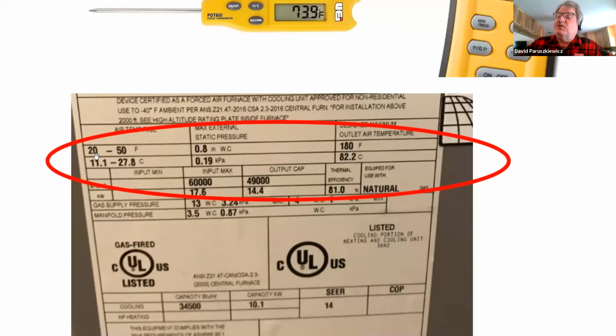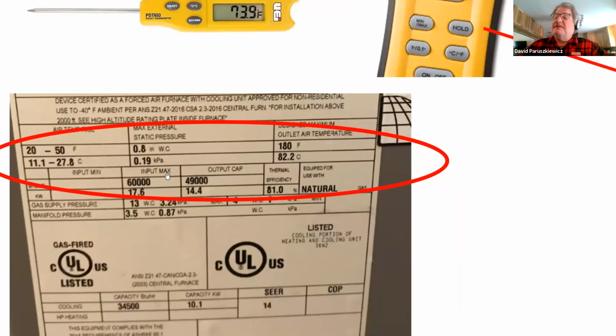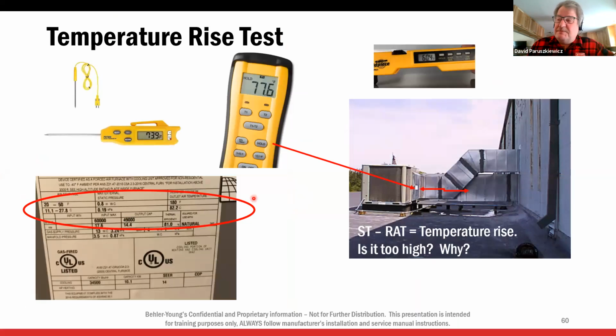Now, if I look on the tag of this particular unit, I'm allowed a 20 to 50-degree rise. So if I have a 40-degree rise, that's not bad. It's kind of in the middle there, right? What if I have a 50-degree rise or 60-degree rise? I'm either overfired or I'm not moving enough air. That's the two things, right? Because if my temperature rise is too high, either I'm overfired or I'm not moving enough air. What if my temperature rise is too low? Then I might not be firing high enough. Now, if my temperature rise is too low, that can also be a problem. It's not going to trip the limit, but I'm not going to heat properly. I could condensate really bad. So this little test is really simple and straightforward.